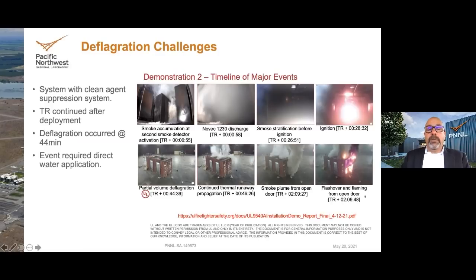What we see here, across these different timelines, is the smoke accumulation. Very quickly, because the smoke detector picks up smoke, the clean agent was discharged. Clean agents have a certain soak time, an ability to maintain a concentration in a space. But after about 26 minutes, we start to see some ignition again, and thermal runaway continues even after the clean agent discharge. That ends up resulting in a partial volume deflagration after about 20 more minutes, with continued thermal runaway. At some point after about 2 hours, they had to terminate the event, and when they opened the door there was some flashover. So in this demonstration, you had thermal runaway and you had deflagration.